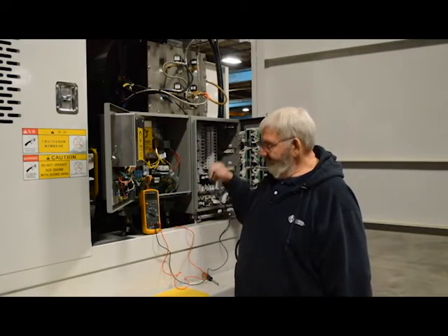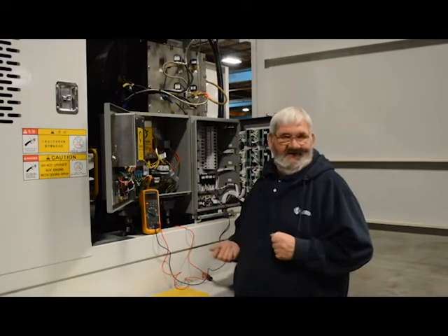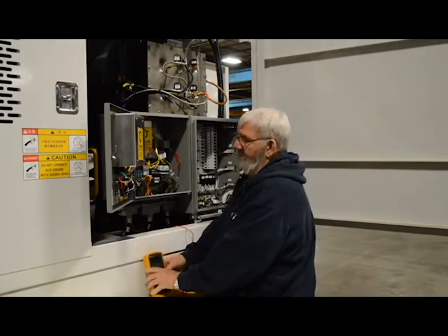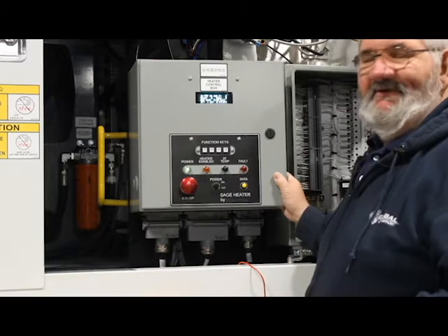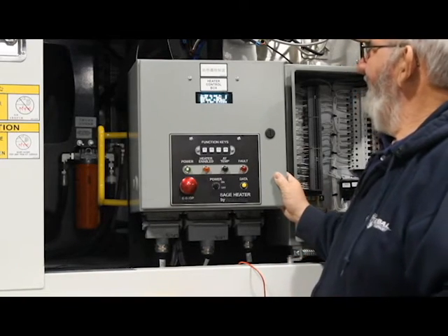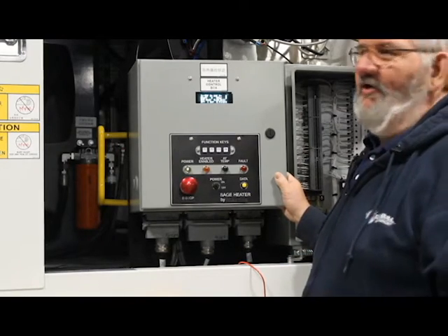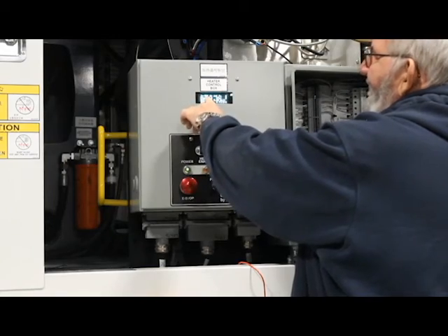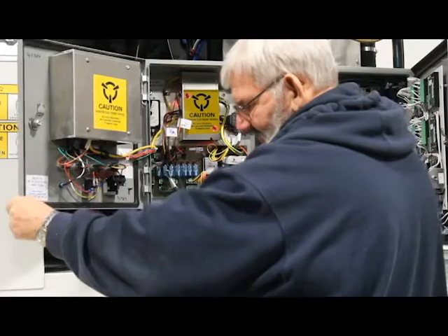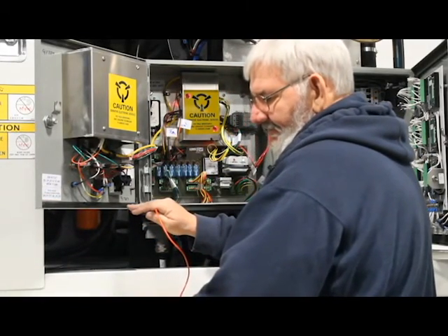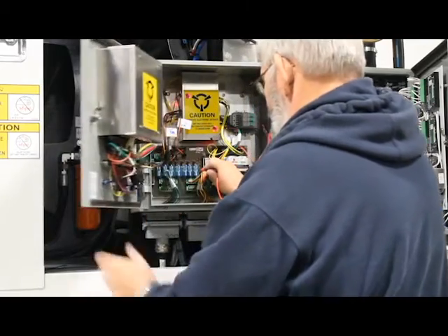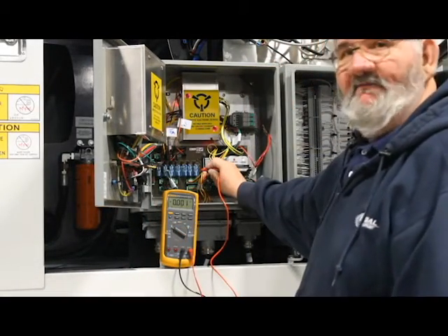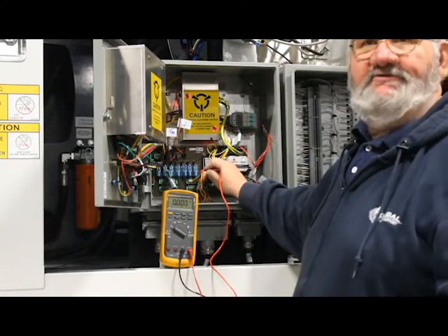Now I'm going to go over here to the side and unplug the Inlet RTD. Before, these two numbers were the same, which is what you would expect to see. The heater's not been running, it's basically a cold truck. But by simply unplugging the Inlet RTD, this number went up. Now if you go to your test point for your Inlet RTD, which is test point number 8, we have no voltage, which is an indication that it's an open circuit.